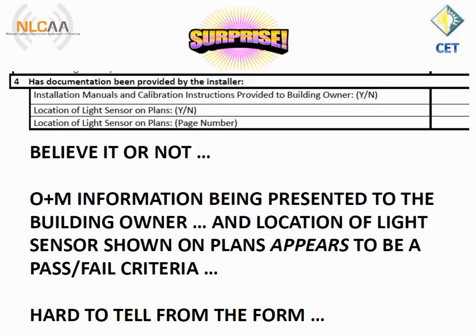There is also a stipulation that sensor locations are shown on the plans, but this is not a pass-fail in the author's opinion. In my opinion, if you put a no in light sensor shown on plans, it's still a pass on the form.